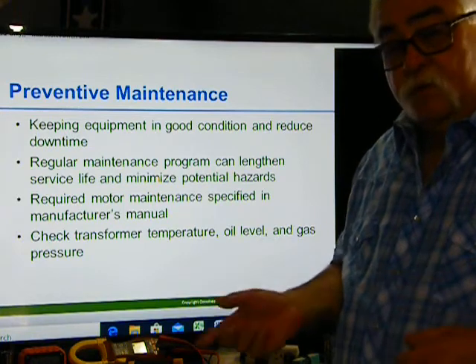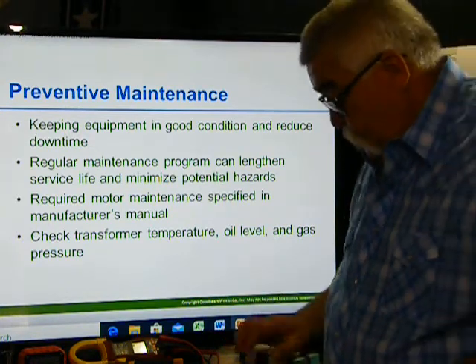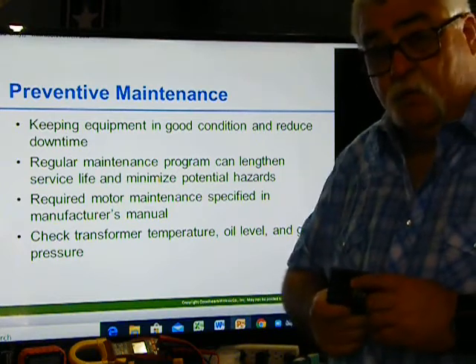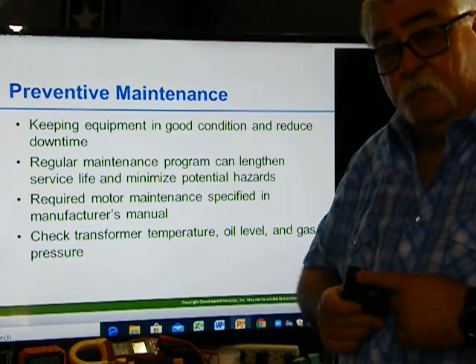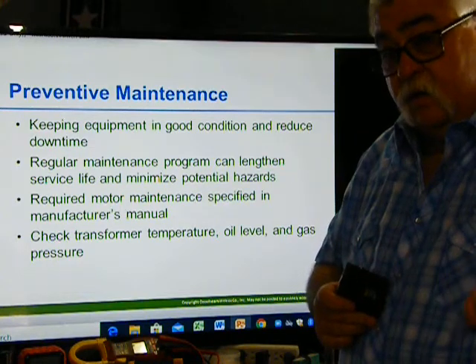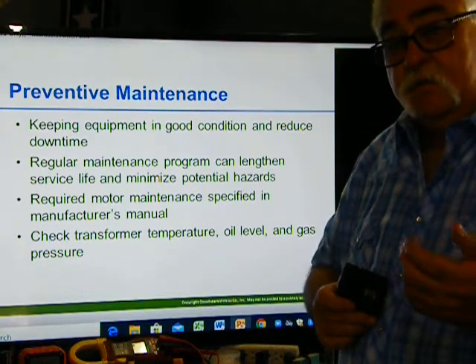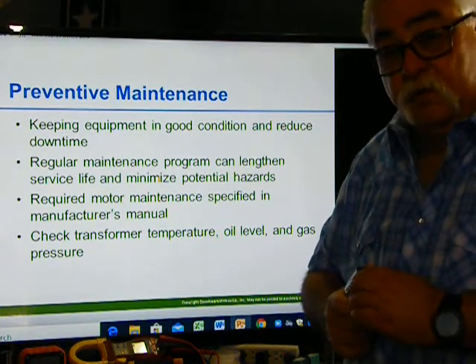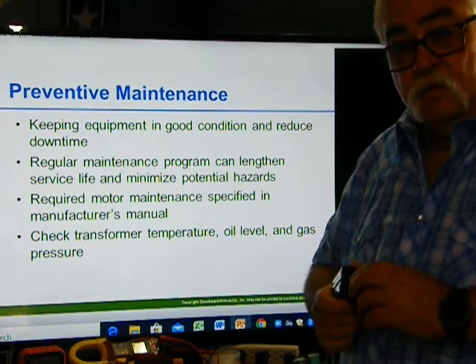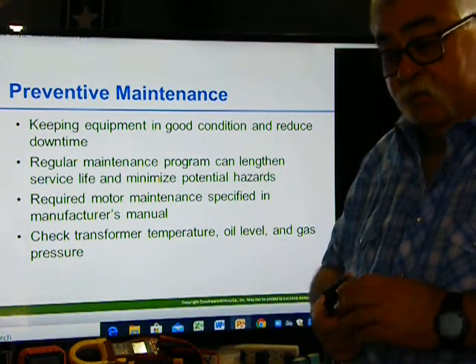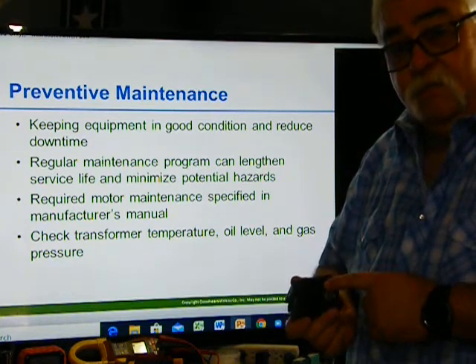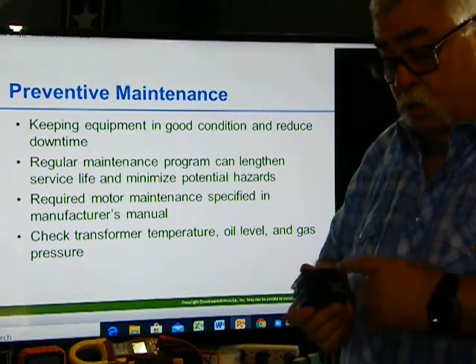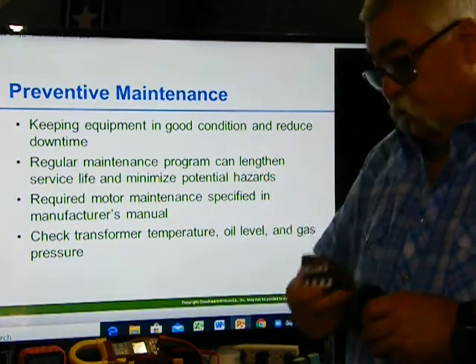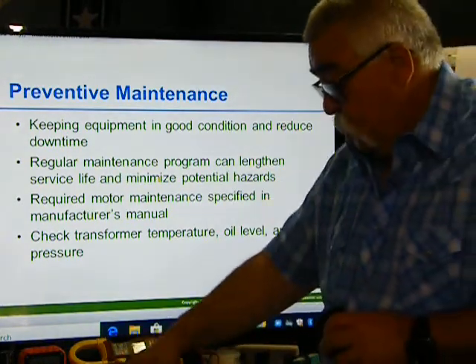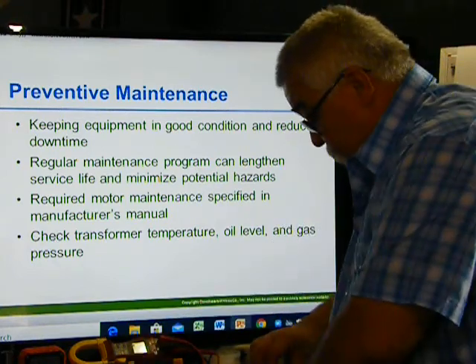Why? Because when we set the breaker, it is not an overload protection for that wire. The breaker is short circuit and ground fault protection, because it's going to be set at 175, 250, or 300%, maybe even 800% if you have an instantaneous trip breaker, of the motor rating. But our wire is only at 125%. So if our breaker is at 250%, we're exceeding twice the amount of what the wire can handle. Why? Well, that's where we rely on the overloads to protect the circuit. So we have to make sure that they're sized accordingly and that they are working accordingly.